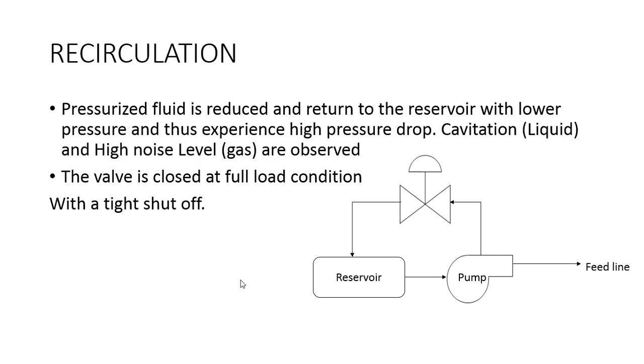There could be cases where recirculation losses are so high that the total output of the system is measurably reduced. Do note that this valve will see the highest pressure drop in the entire plant when we bypass the main pump. The cost of fluid leakage through this valve may exceed the purchase price of the valve many times over, through loss in reduced plant capacity, unavailable load and the increased pumping power required to pressurize the fluid. It is not an application where the engineer should compromise on valve selection, and must select a solution for long-term seat integrity to assure leakage-free operation.